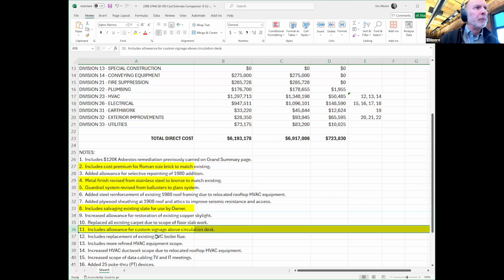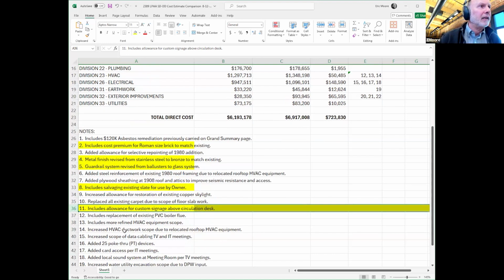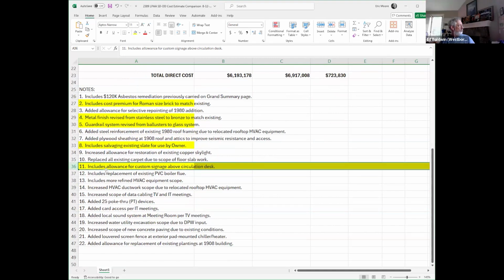We included replacement of the existing PVC boiler flue. Right now your existing gas boiler vents through a PVC pipe that runs up inside one of the masonry chimneys, and it's not high-temperature PVC, so it's not the right type. We've included replacing that—it's a requirement.